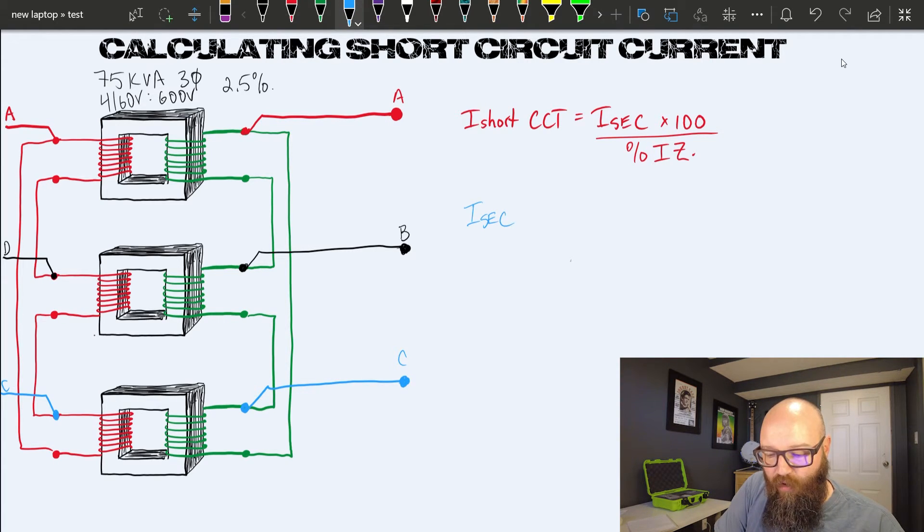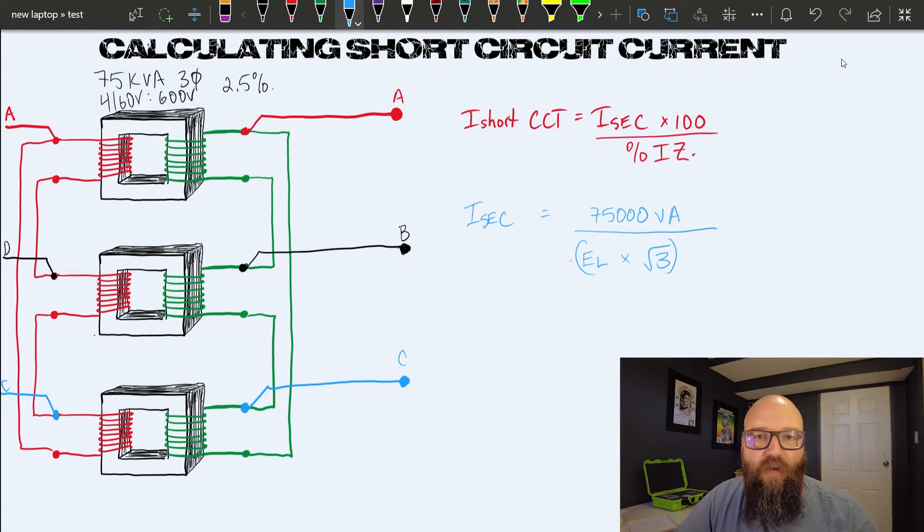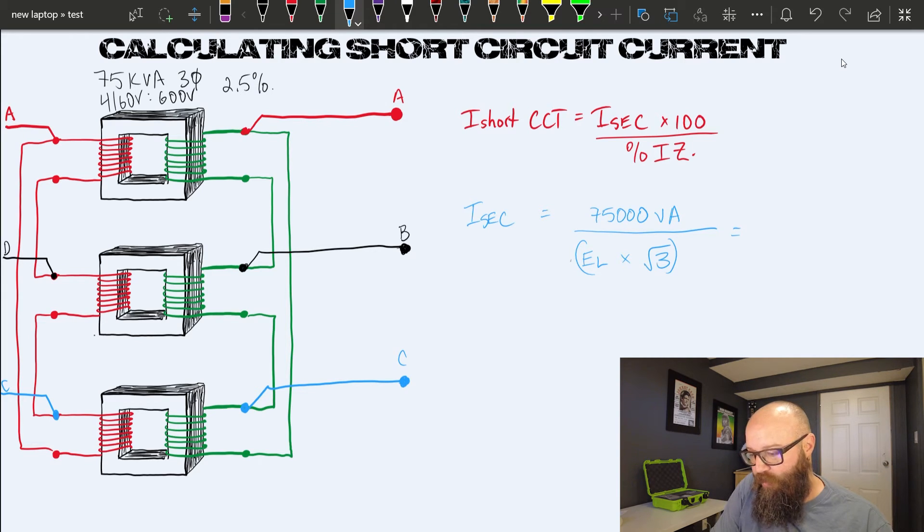The current on the secondary equals the kVA rating of the transformer—75,000 VA—divided by E line times root three, because it is a three-phase transformer. If you're punching this into your calculator, it's crucial that you don't forget those brackets so your calculator follows the proper sequence of operations. So 75,000 divided by E line times root three gives us around 72.17 amps. That is my rated secondary current on this transformer.